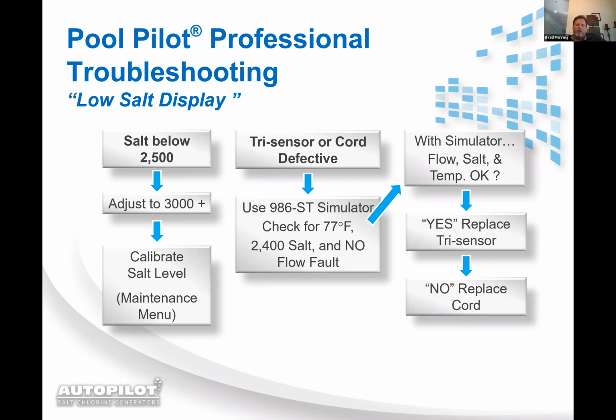Once you calibrate it, you should be able to plug the tri-sensor back in, and it should come closer to the manual readings that you got when you did a test. If you plug the simulator in and the unit is reading the simulator perfectly, it means there's not an issue with the power supply. There's nothing to correct there. It means you have a tri-sensor issue. There's only one or two things that could be wrong with the tri-sensor if it's not reading the right salt. Either it's scaled up or it's fouled.